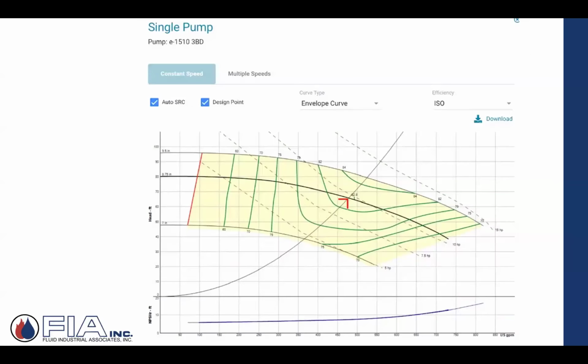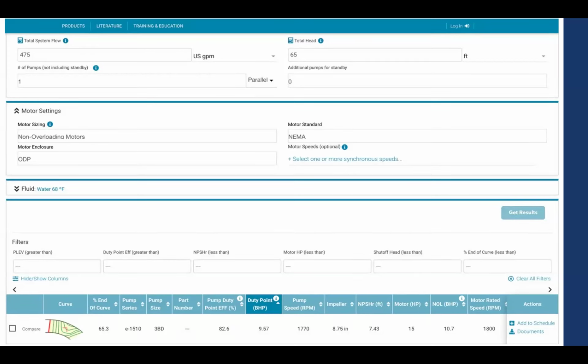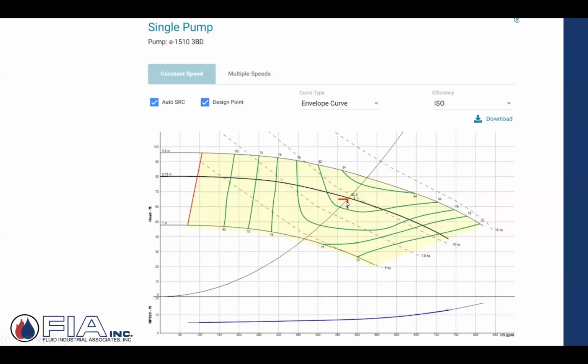The next option would be, hey, I want to pick it at a non-overloading selection. And where this comes into play, all of a sudden, look at this motor horsepower that you've picked. It went from 10, which is adequate, 475 at 65. It says, hey, let's be safe. Let's pick a non-overloading motor. I'm going to bump it up to 15. And here's the reason why. At that duty point, this is the impeller that I need, 8.75 inches. If I follow this curve and I start to move past that duty point, I quickly can pass that 10 horsepower, which is these dash marks right here. If I start to drift past that, I can overload that motor, I can overheat it, and I can shut it down.